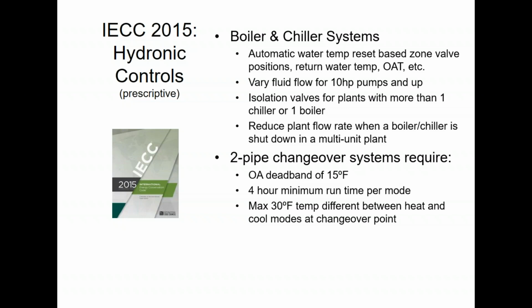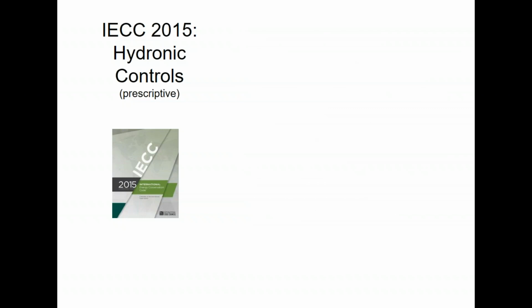You have to have a minimum wait time before you change over. You have to have a minimum temperature before you change over between the two. Because we don't want a system that's been heated up with the boiler and then immediately cut over to the chiller. It's very wasteful. Right? So they have those kinds of limitations.